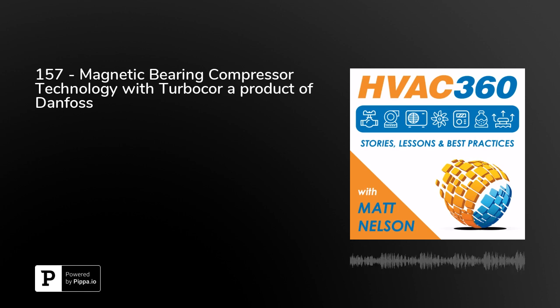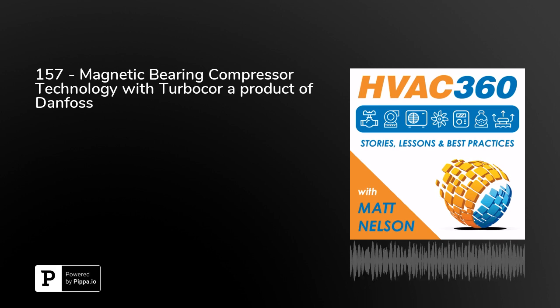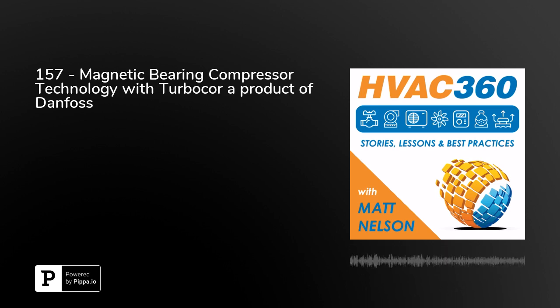Now, just out of curiosity, where is the high lift being applied? So the high lift compressor is one we actually launched last year, and the specific applications it's optimized for are, just like its name suggests, high lift - meaning the difference between your saturated discharge temperature and your saturated suction temperature. In other words, there's a big pressure ratio difference between your high side condenser and your evaporator.